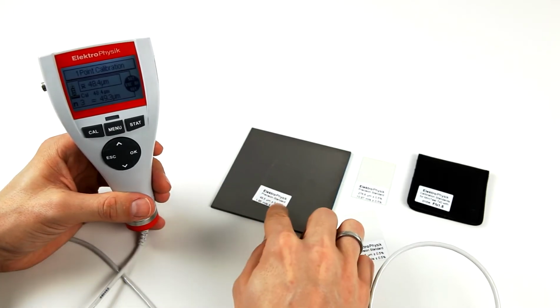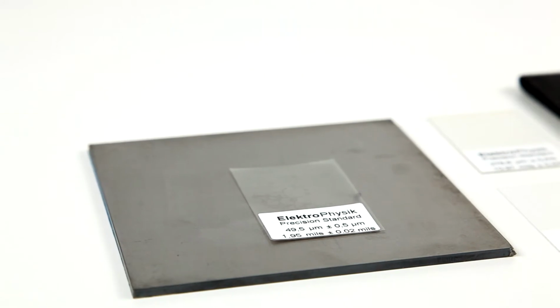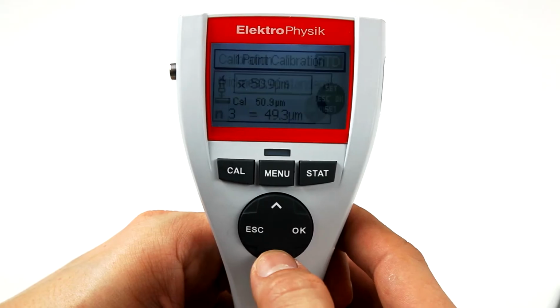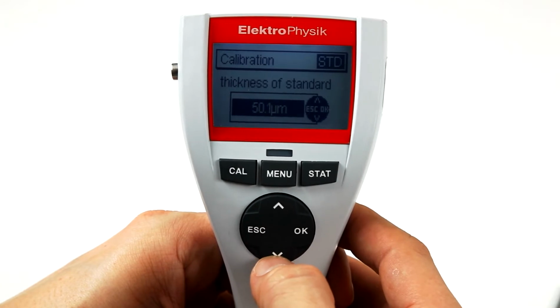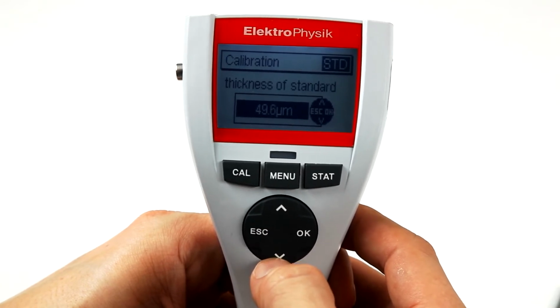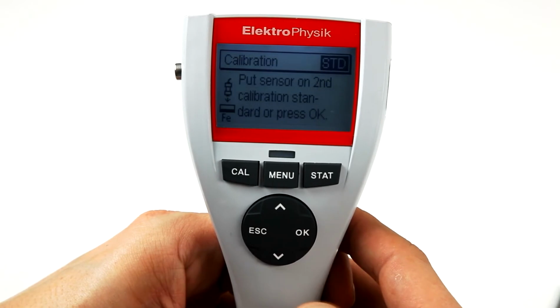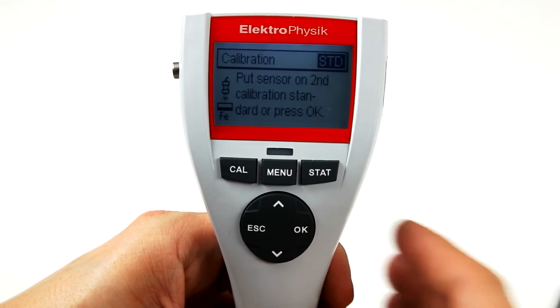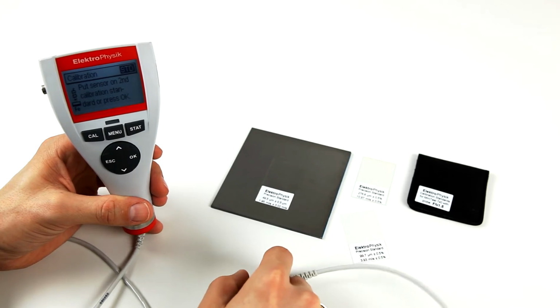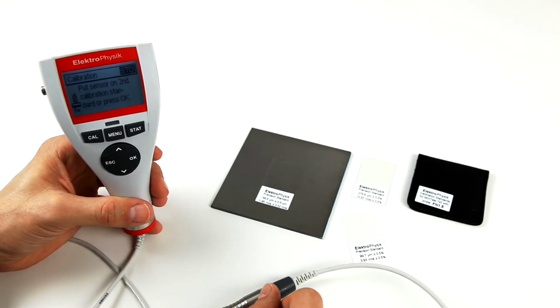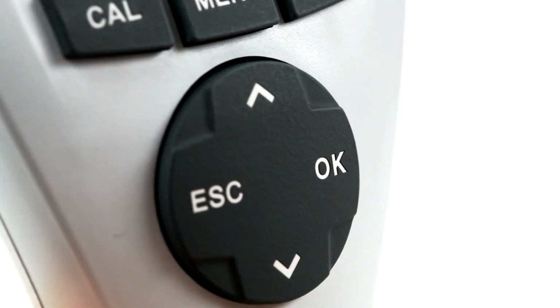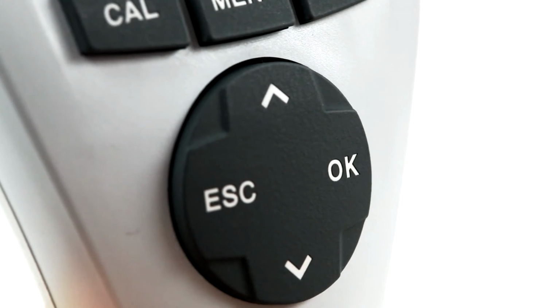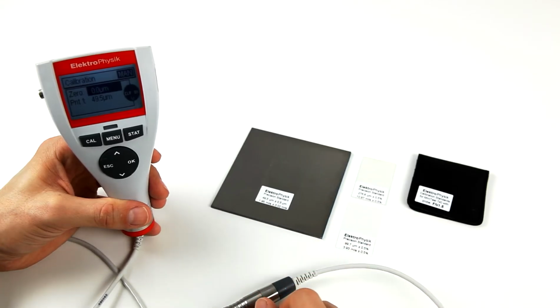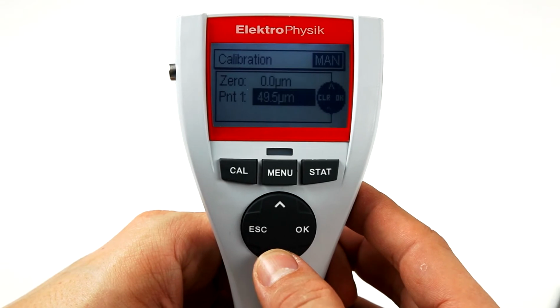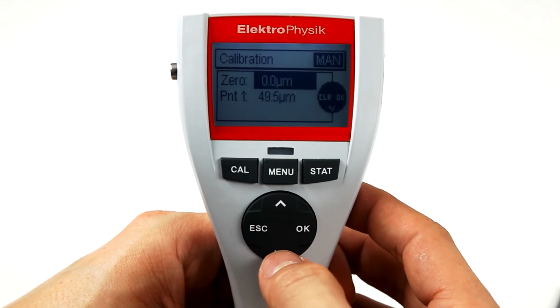Adjust the displayed value to the thickness value indicated on the calibration foil using the arrow keys. Press OK to confirm the settings. The gauge now offers to register a second calibration point. You can continue with the second calibration, or you can skip the second calibration point by pressing OK. All values you have registered during the calibration process are now summed up by the gauge. Confirm these by pressing the OK key.